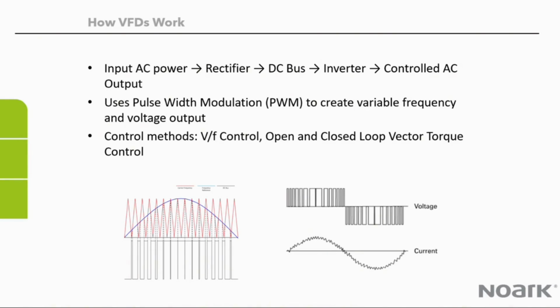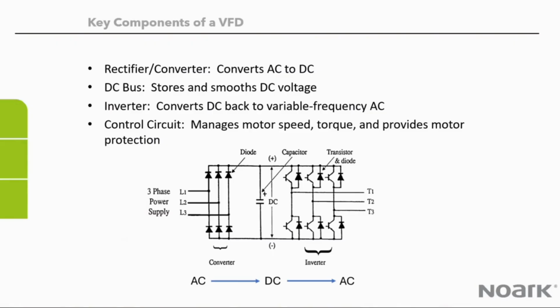Control methods. We have volts per hertz, or frequency. You have open and closed loop vector torque control, which is for more precise applications where we have to regulate torque. Open means there's no encoder feedback, and closed means there is. With closed, you get better performance. But for most applications, just volts per hertz, or sensorless vector, which I forgot to add in here, are other options for control.